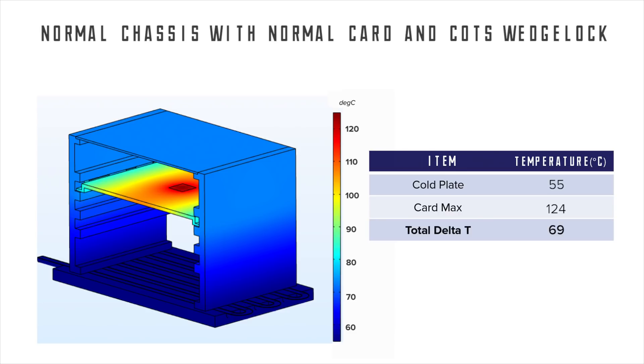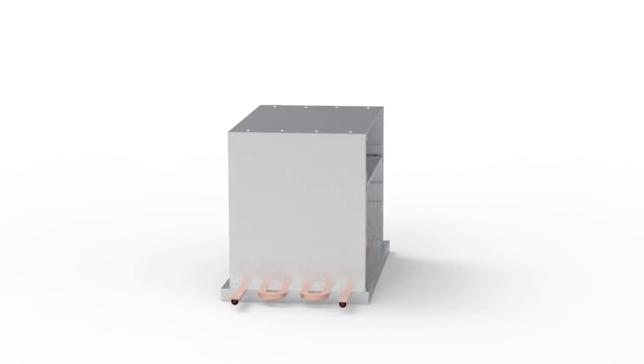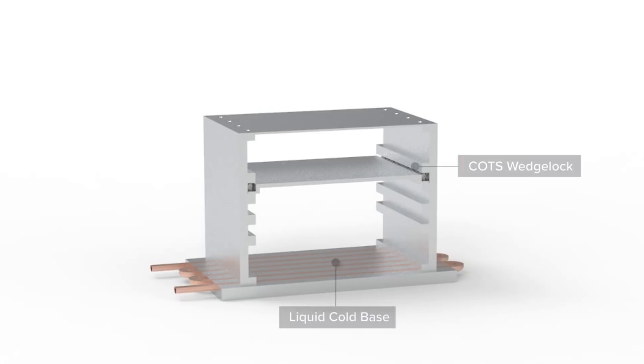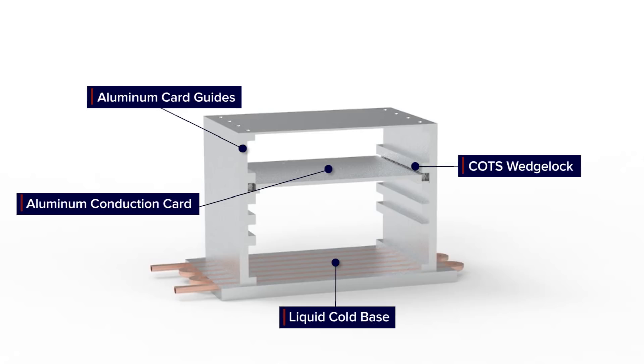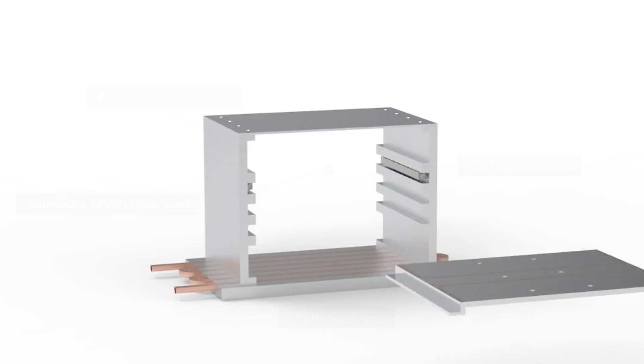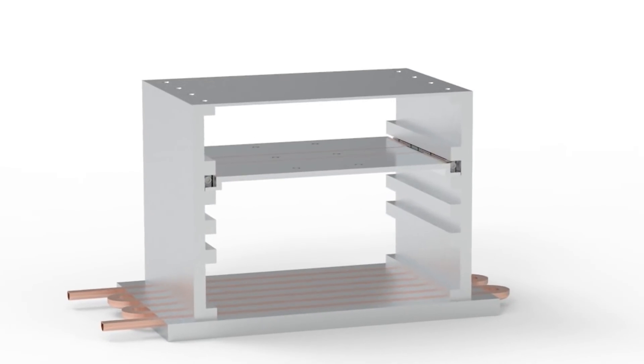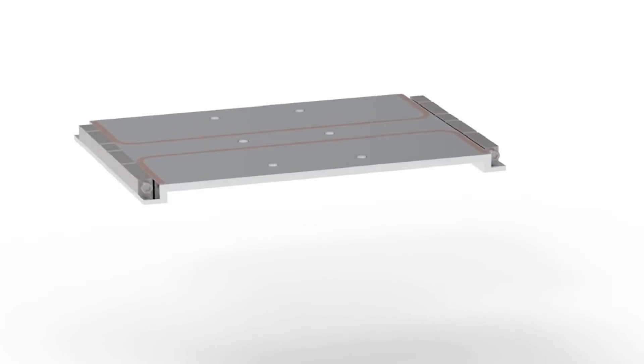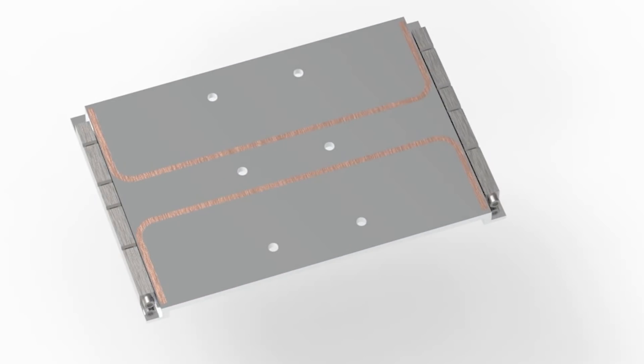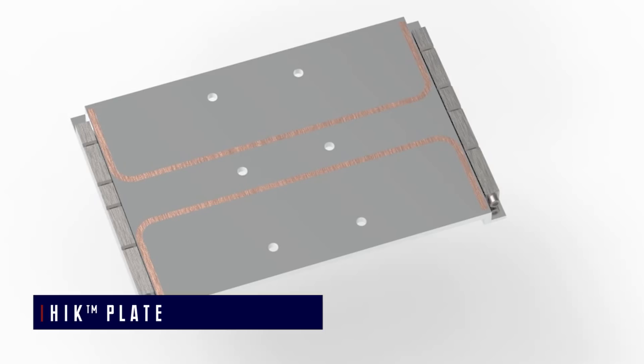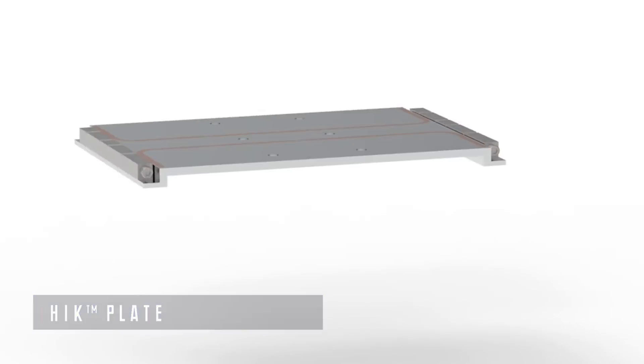Therefore, designers must find a way to reduce the thermal resistance. The largest delta T in the system is from the centralized component to the card edge, which means the design is limited by the thermal conductivity of aluminum. By strategically embedding heat pipes, you can greatly enhance the bulk thermal conductivity of the heat spreader. The resultant embedded heat pipe card frame is known as a high thermal conductivity or high K plate.